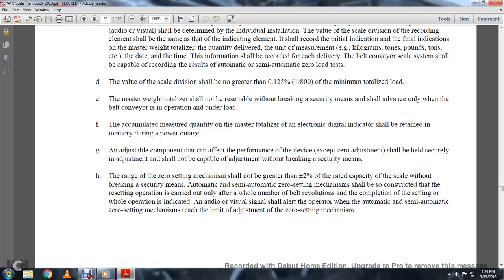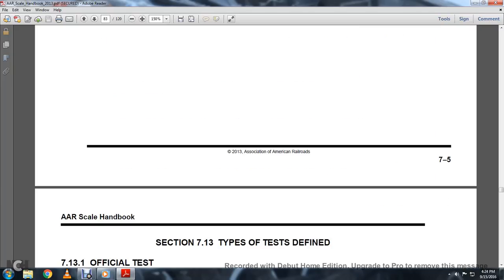The range of the zero mechanism shall not be greater than plus or minus 2% of rated capacity. The scale shall have automatic or semi-automatic zero setting. The mechanism will be constructed so that resetting operations are carried out over whole number revolutions. The completion of the setting operation shall be indicated by an audiovisual signal to let the operator know when the automatic or semi-automatic zero setting mechanism has reached the limit of the adjusting range.